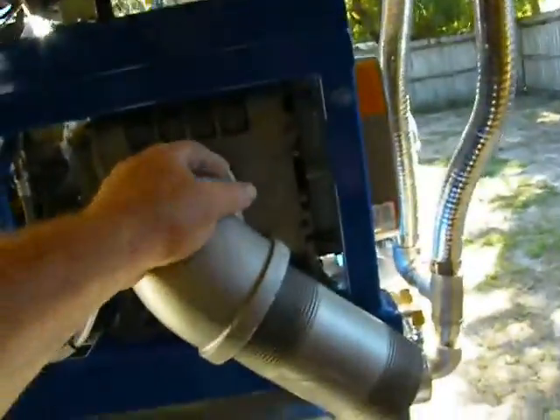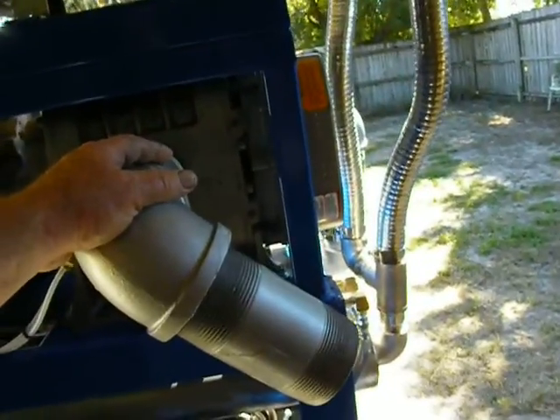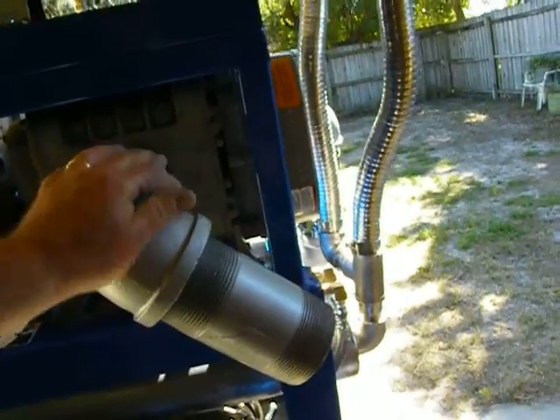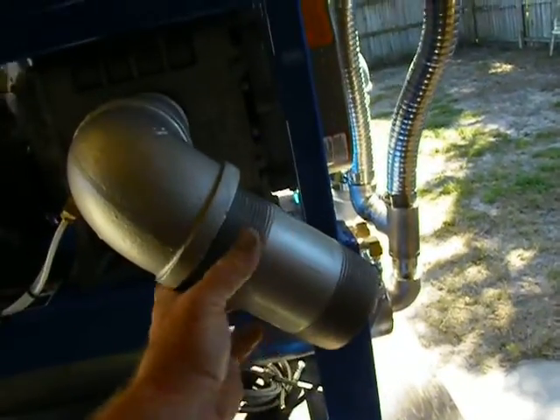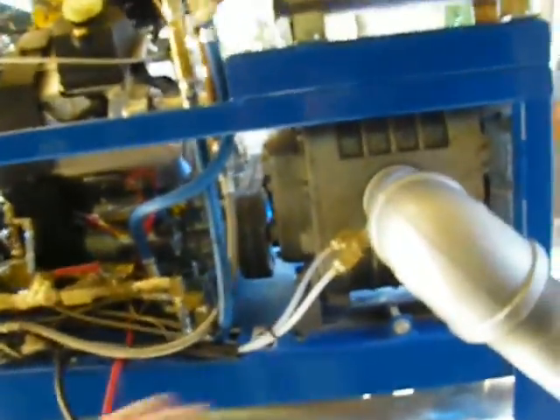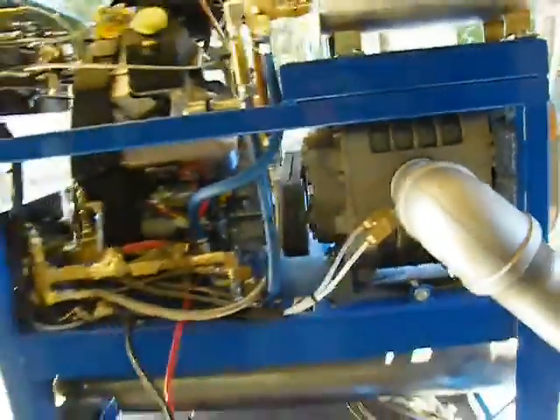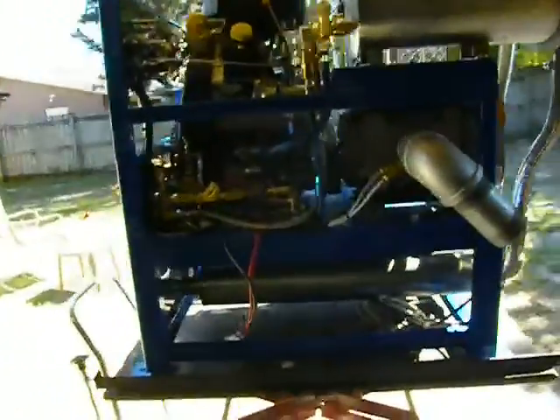As manufacturers suggest, a lot of these companies are putting preheaters on with obstruction and lower inlets. The inlet is a reduced diameter size, which affects the differential and causes the high and low pressure system to be offset, creating an enormous amount of overheating.